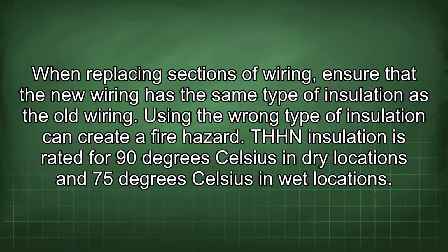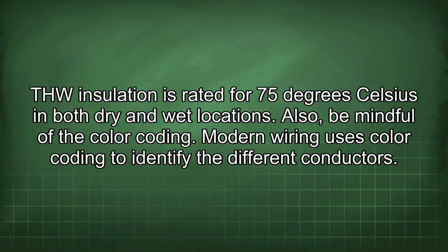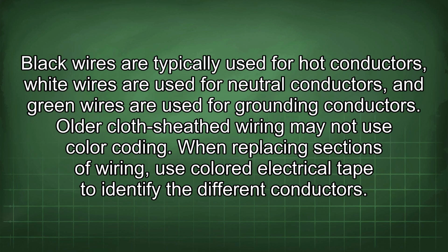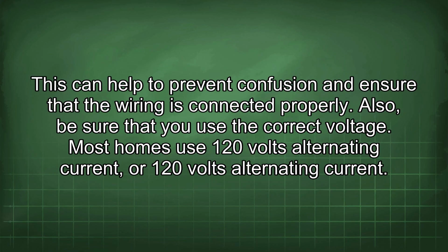THHN insulation is rated for 90 degrees Celsius in dry locations and 75 degrees Celsius in wet locations. THW insulation is rated for 75 degrees Celsius in both dry and wet locations. Also, be mindful of the color coding. Modern wiring uses color coding to identify the different conductors. Black wires are typically used for hot conductors, white wires are used for neutral conductors, and green wires are used for grounding conductors. Older cloth-sheathed wiring may not use color coding. When replacing sections of wiring, use colored electrical tape to identify the different conductors. This can help to prevent confusion and ensure that the wiring is connected properly.